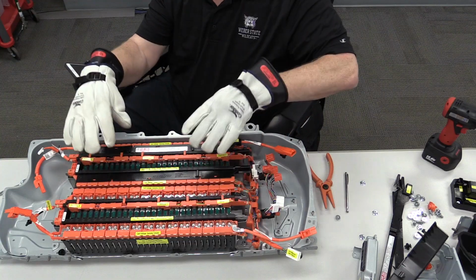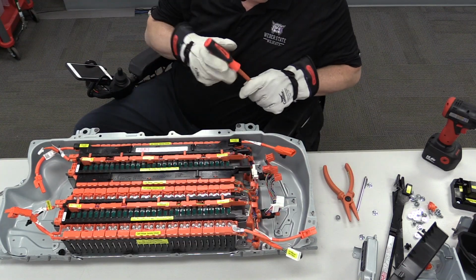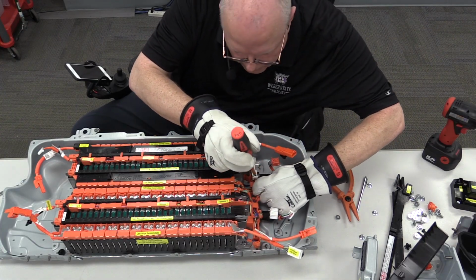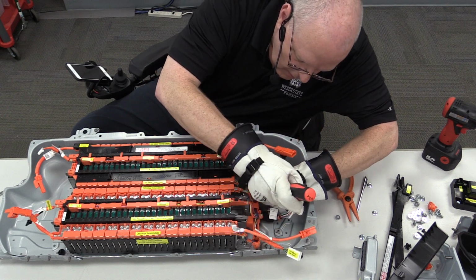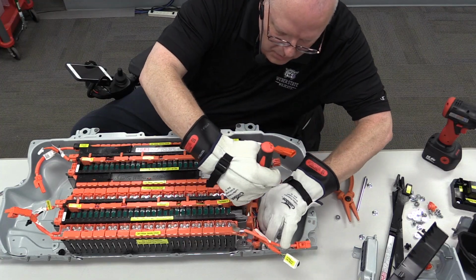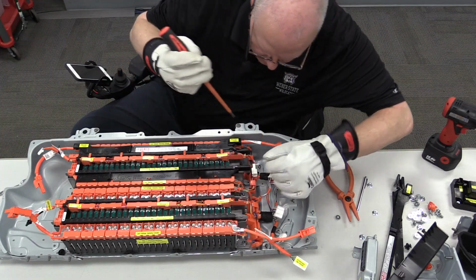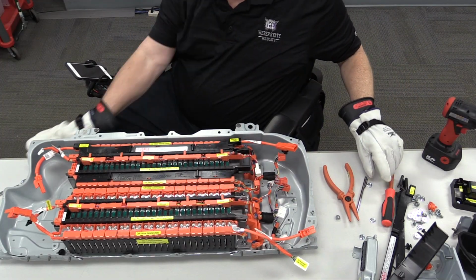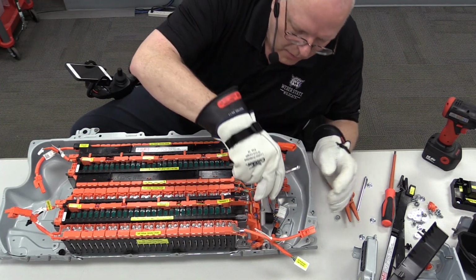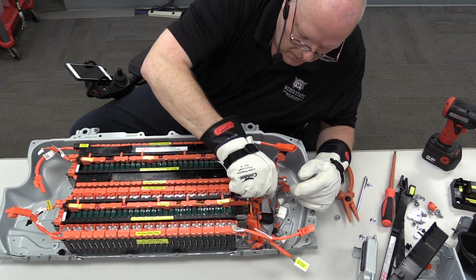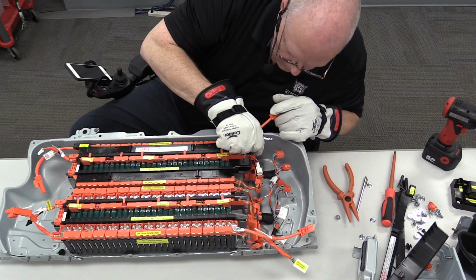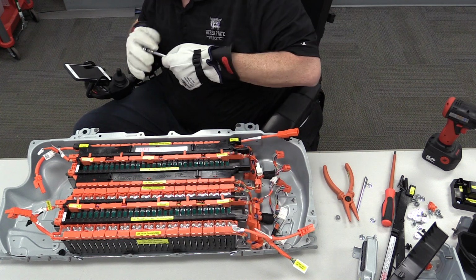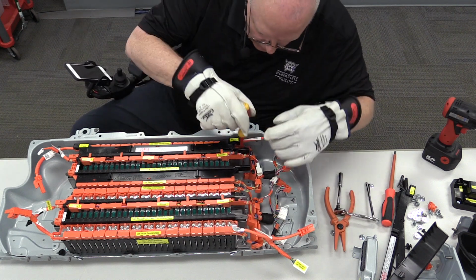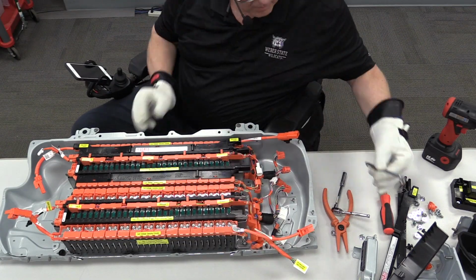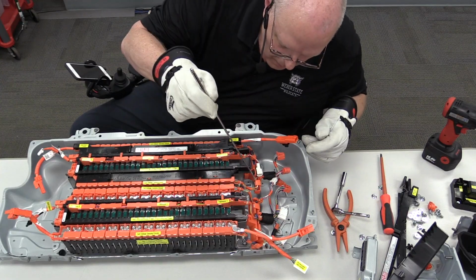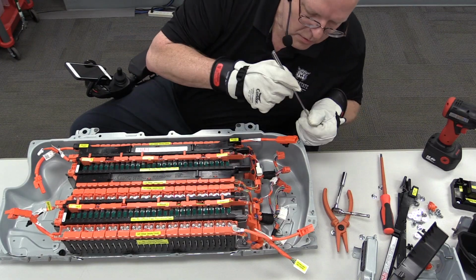This battery stack is held down with 4 bolts, and this one's held down with 4 bolts. We've got a couple of clips over here that hold all these harnesses to the case itself. So let me undo the clips. There's one. There's the other one. And now we just come down and loosen all 4 of these bolts, staying away from those battery terminals. Let me take these out while I'm here. All right, we'll get those nuts out of there so they don't fall in the wrong location and cause a short circuit somewhere.